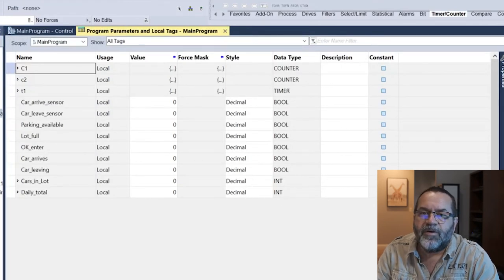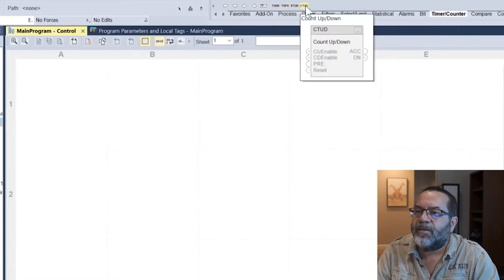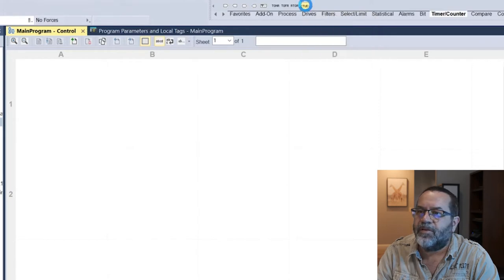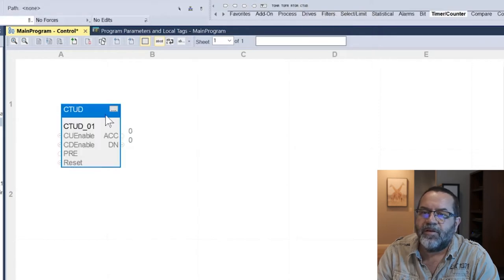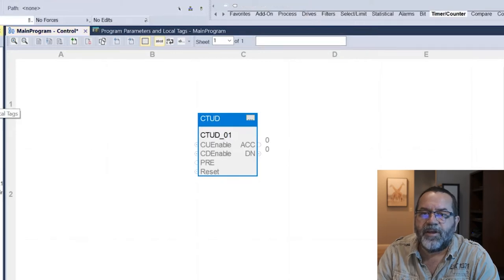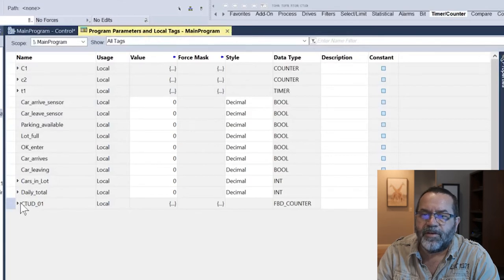Going to my tags — right now I have two counters, timers, booleans, and two integers. I'll go to my control and I'm going to add a CTUD — that's count up/down. I just clicked on that and it put it in the middle. Now if I go back to my tags, notice down at the bottom I've now got a tag for this block, so I didn't have to make a tag — it created one for me.